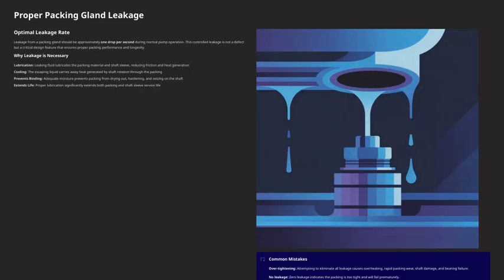Let's talk about proper packing gland leakage. Ideally, during normal pump operation, you should see about 1 drop of fluid per second leaking from the packing gland. Now, this might seem like a problem at first, but actually, it's a critical part of the design. That controlled leakage helps ensure the packing performs well and lasts longer. So why is this leakage necessary?